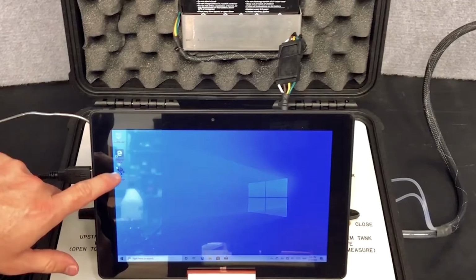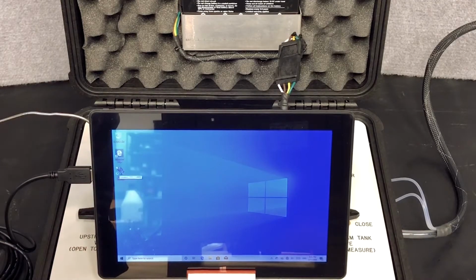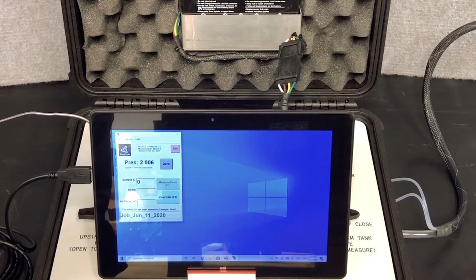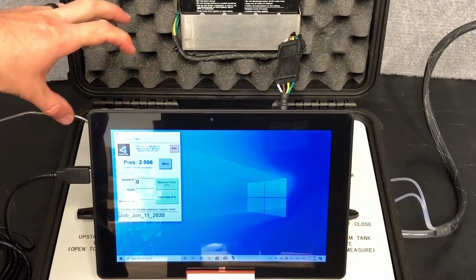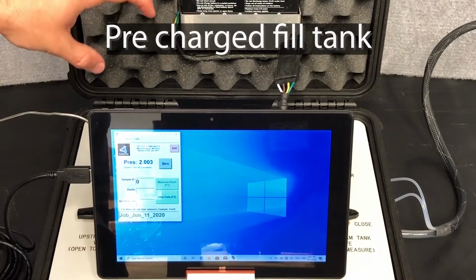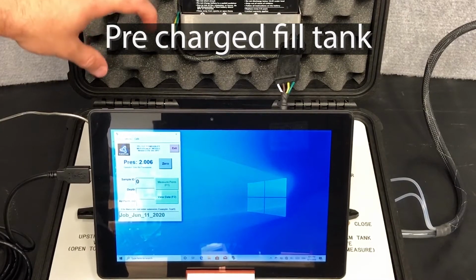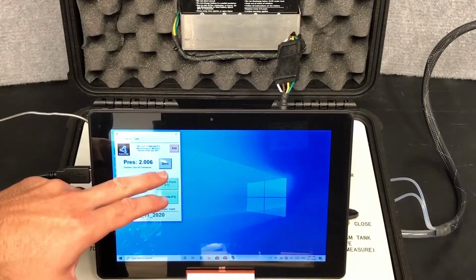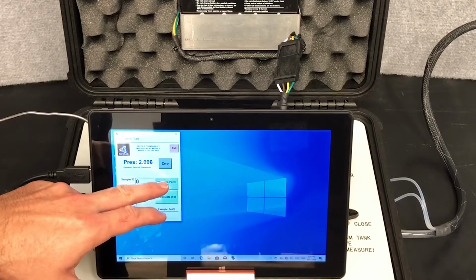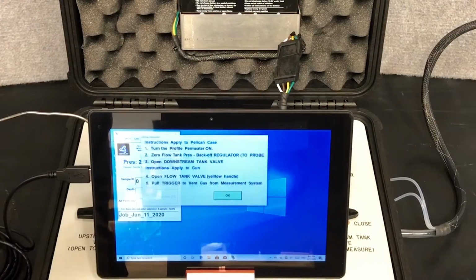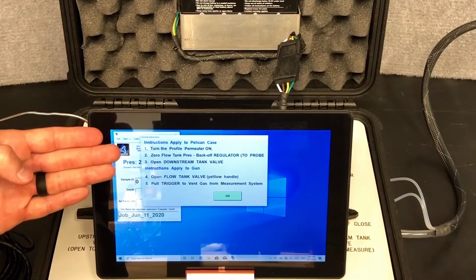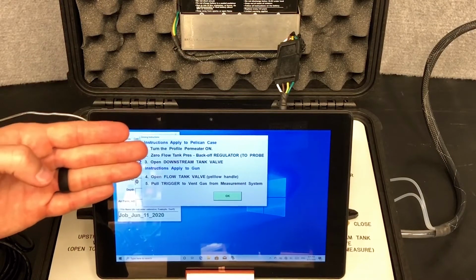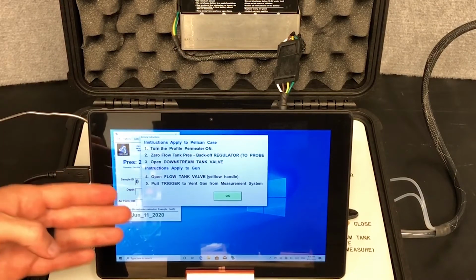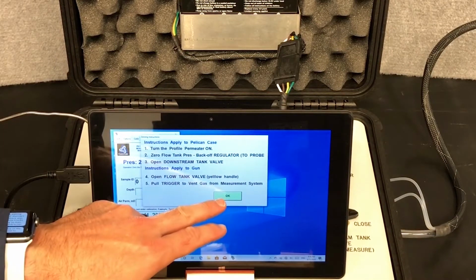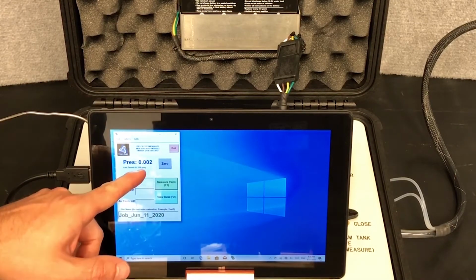So we'll bring up the tablet, the computer, and open up the PPP software. Right now we just have pressure on that inlet pump, so there's no pressure actually on the system yet. The first thing, you can't hit measure perm, it won't let you. So first you have to zero the actual transducer, and then it'll give you instructions on how to get rid of all the pressure on the system. If there is any - we know there's not right now - so we'll just hit OK. So it's zeroed the pressure.